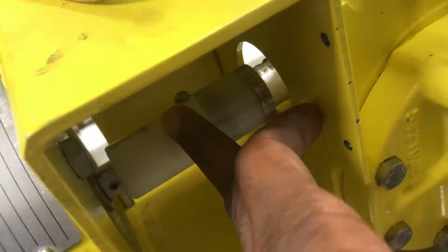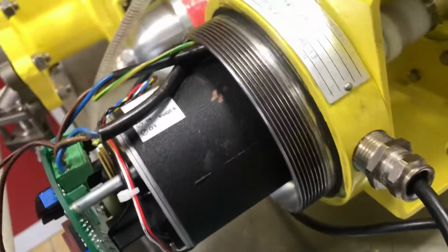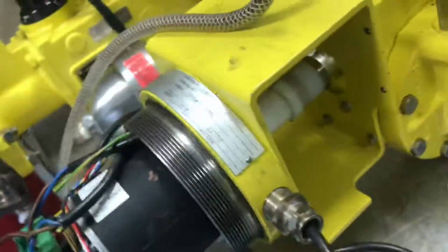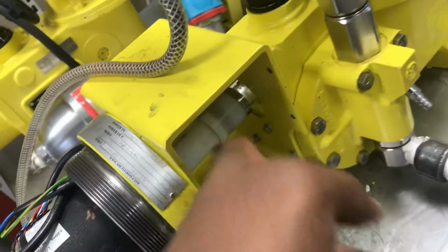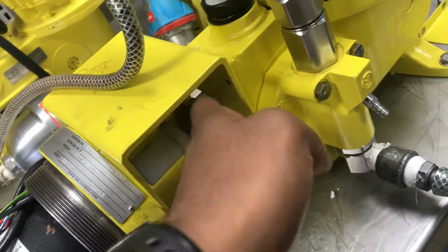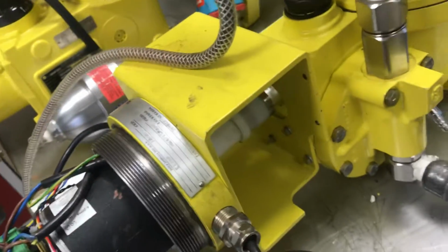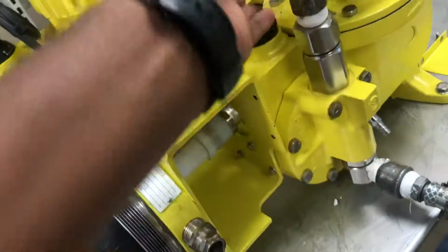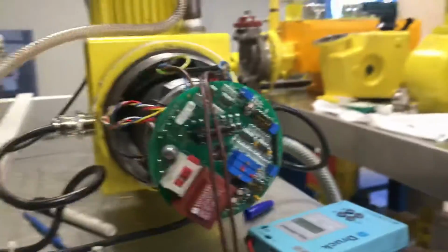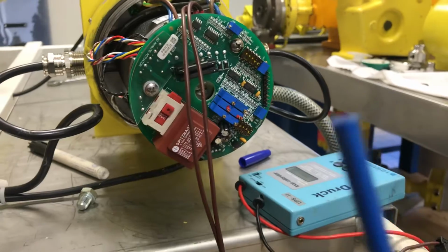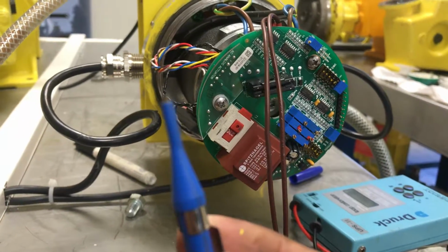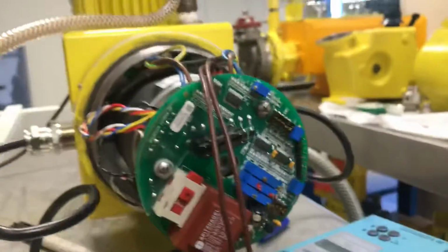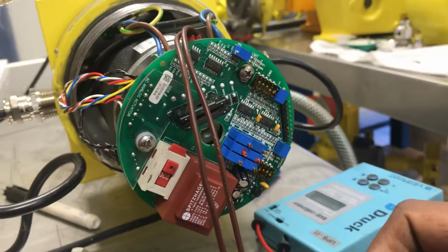Before doing the calibration, you have to dismantle this connection and make the calibration separately, then connect with the motor, I mean with the pump. Why? In the sense, if you connect with the pump and something goes wrong, it will damage the pump parts, coupling, or internals. Now you need a small screwdriver to adjust the potentiometers. Okay, now we need to make it 0.